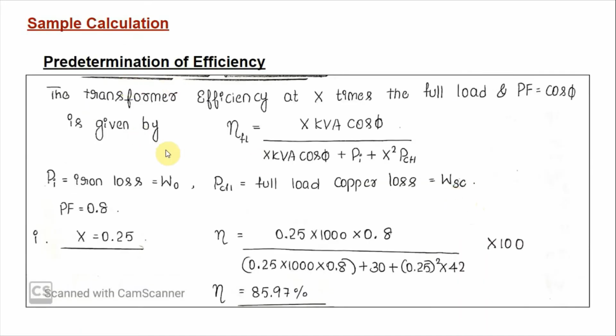So this is the sample calculation. So first we've got the iron loss. From the iron loss and the full load copper loss of each transformer, we'll calculate the efficiency. So we'll start with X equal to 0.25. All these parameters will remain the same. The only thing is we have to substitute the X value in each calculation. So that way we'll calculate the efficiency for each load value, and then we'll calculate the regulation using this expression.